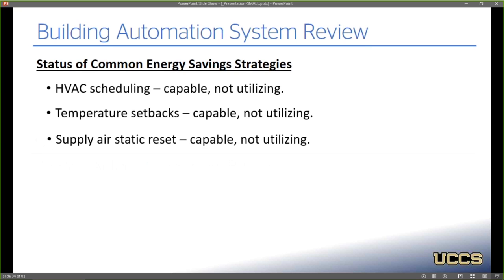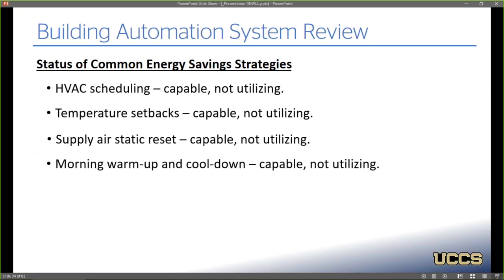There is a supply static reset algorithm programmed in, but due to the set points that they have plugged into the algorithm, it's not actually doing anything. You're probably noticing a trend here. Morning warm up and cool down, because they're running everything 24/7, they're not actually using it, even though it is programmed in there.